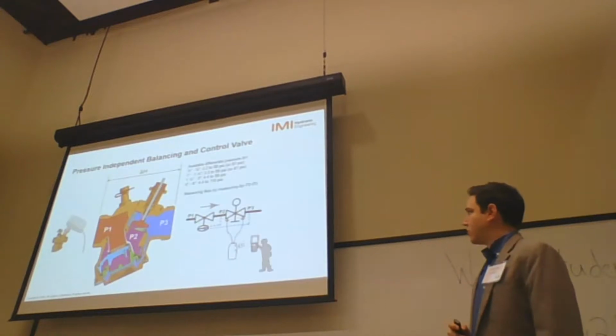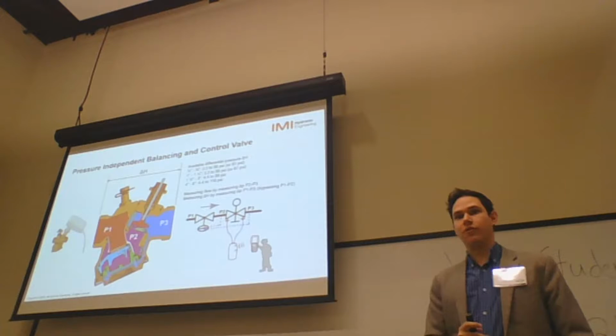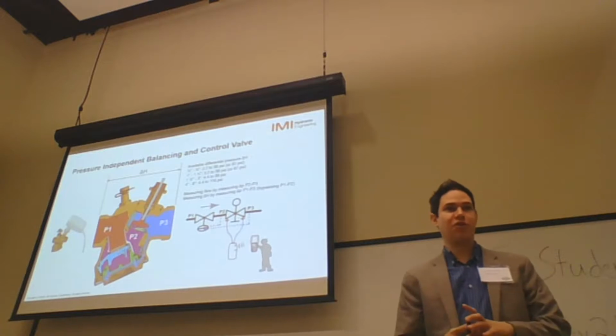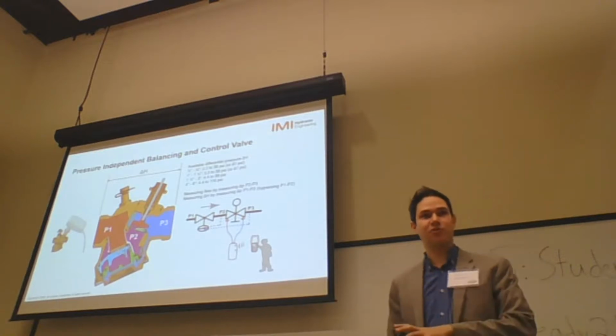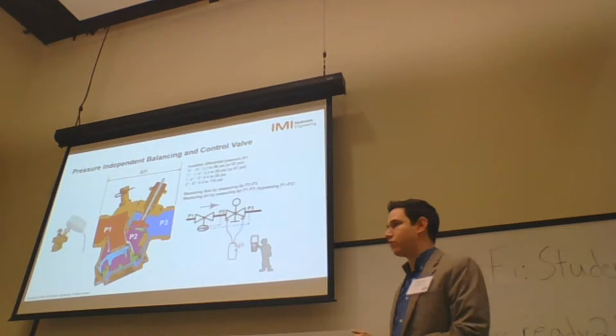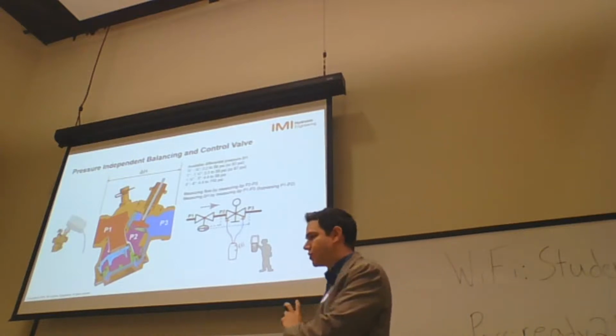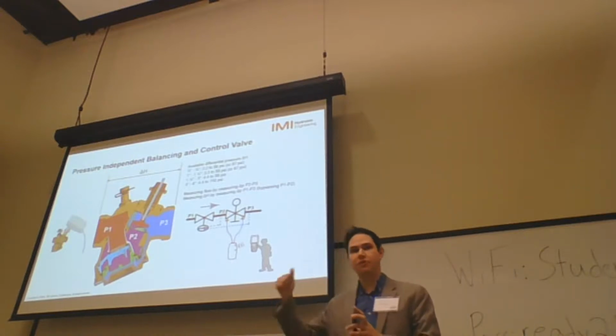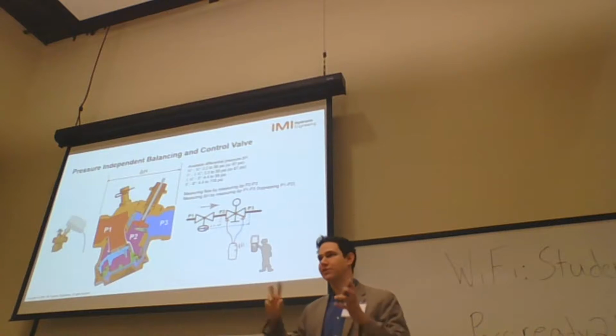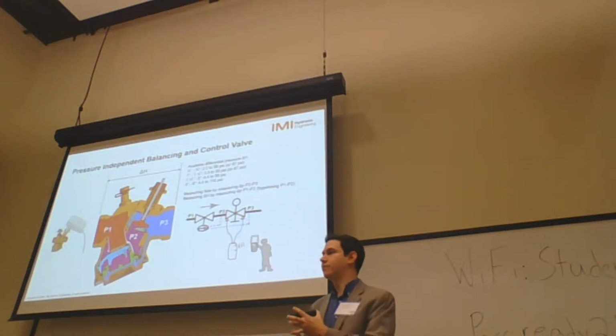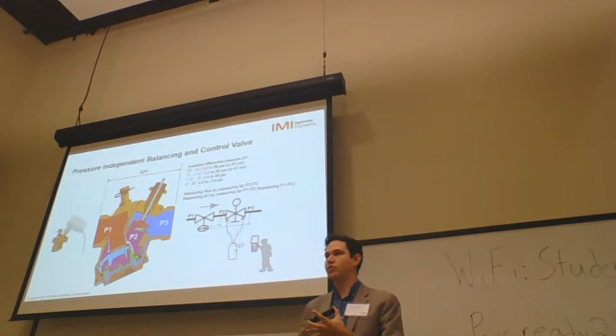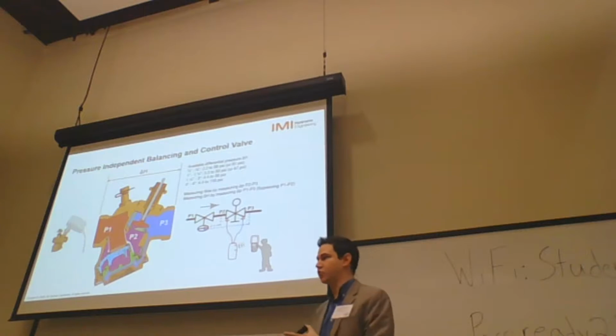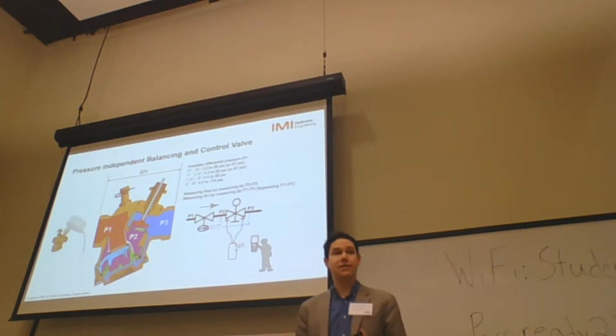So let's now talk about the pressure independent control valve. I'm sure that most of you heard of or played with that before as well, pressure independent control valve for hydronic. Just giving a little bit of history. The differential pressure controller was invented or created in 1993. The pressure independent control valve around 1994.